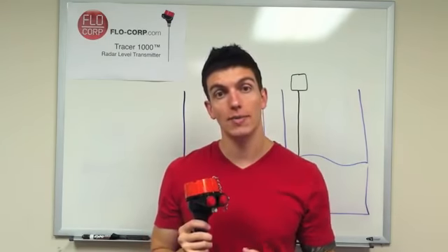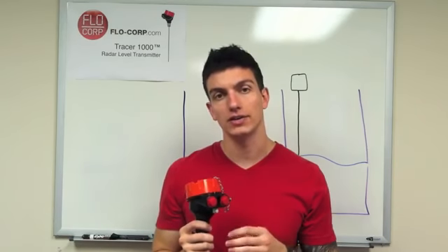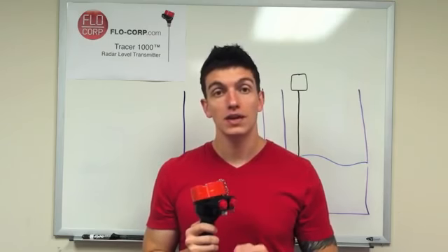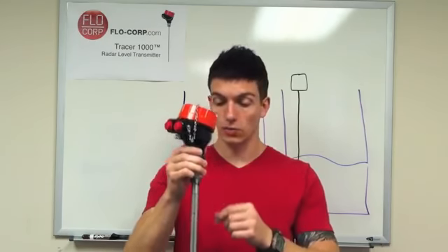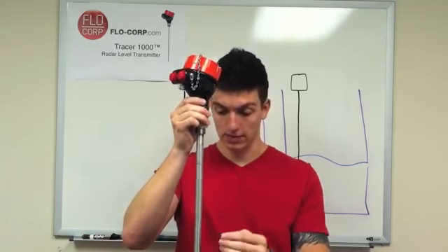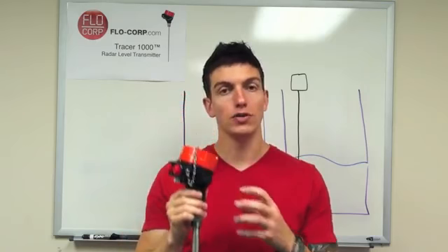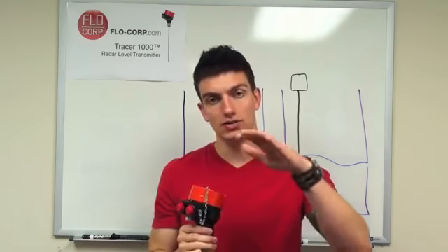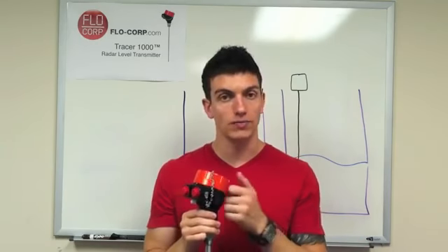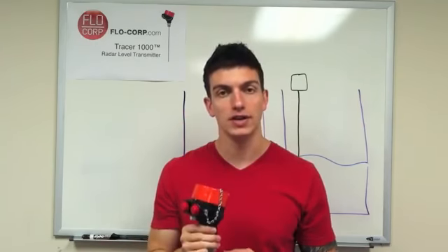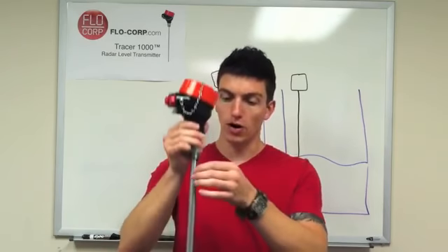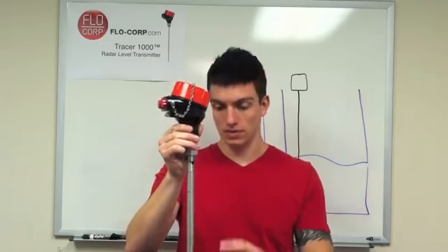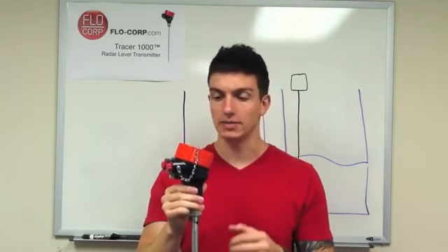This is also a good time to talk about contacting versus non-contacting level meters. The ultrasonic transducer we saw is a non-contacting level meter. Essentially, there are no physical hardware parts in the media that you're measuring. The difference with the guided wave radar is that we do have the probe inside of the media that we're measuring. Even though in both cases the energy touches the surface of the water, because there's no actual hardware inside of what you're measuring, the ultrasonic is considered non-contacting. Because the probe extends through the liquid that you're measuring, the guided wave radar is considered a contacting meter.